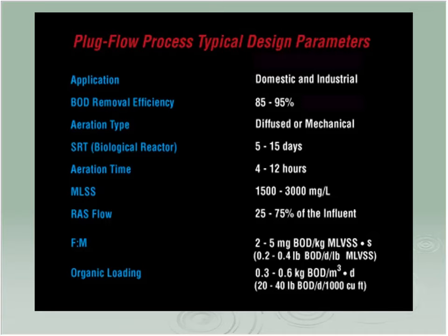We have recycled streams for various reasons. And here's a new term that we haven't even mentioned yet. F to M, that stands for food to microorganism ratio. And this is the typical range in conventional, 0.2 to 0.4 pounds of BOD per day per pound of volatile suspended solids. We don't want too much or too little food for the number of bugs that we've got in there that are actually alive and working for us. So that's actually a control point for us.